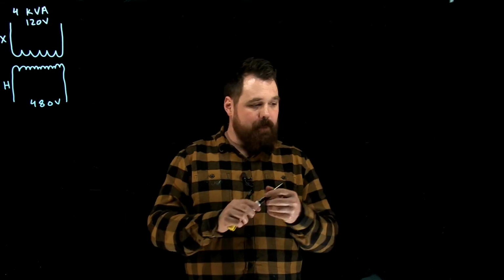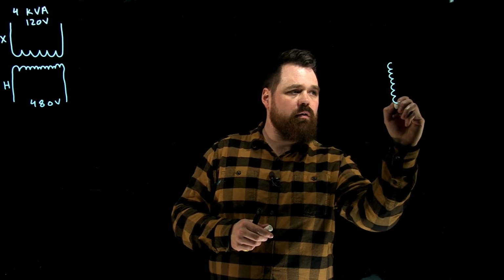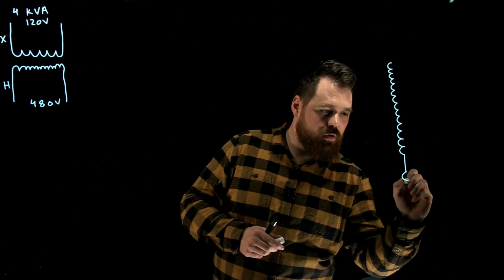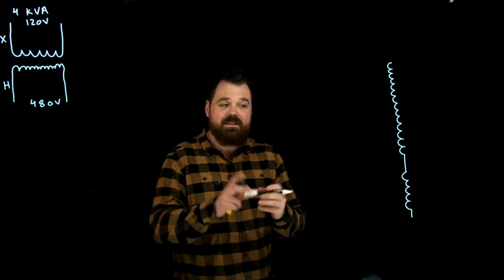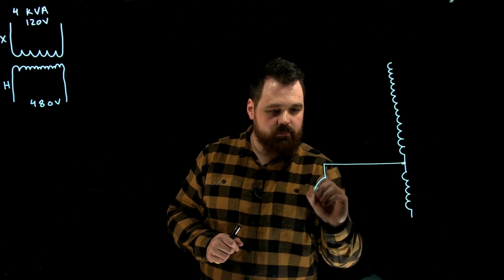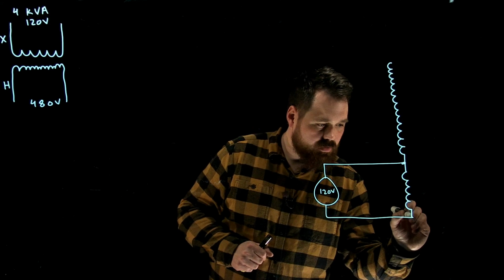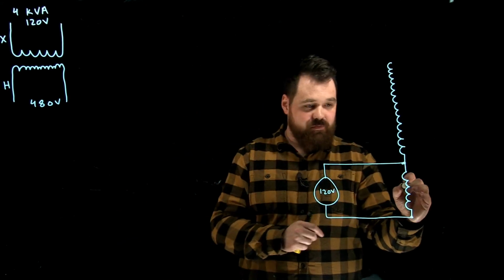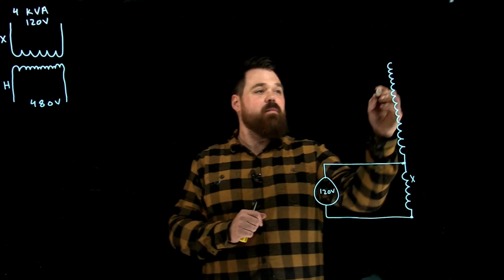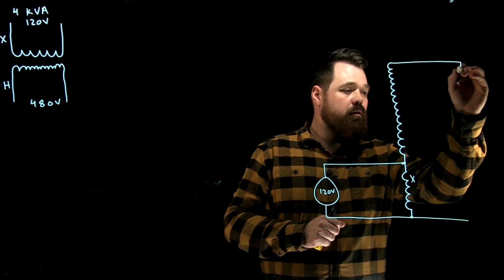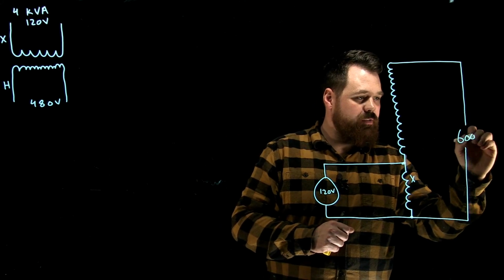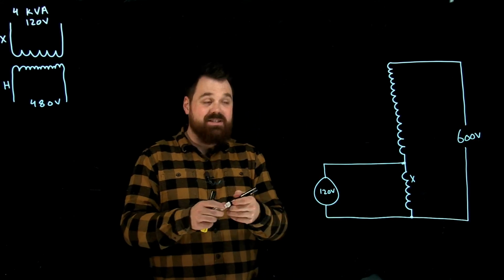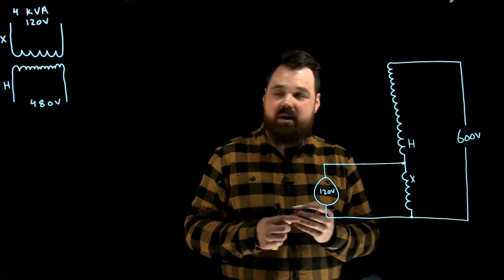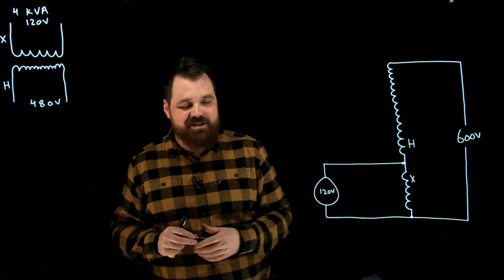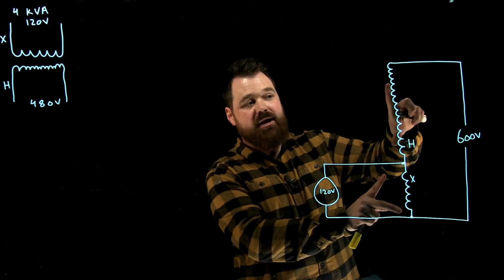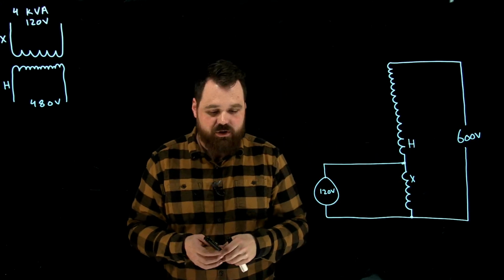Now we know an auto transformer is one big common winding. And I'm going to draw it like this, right? So we are going to take a 120 volt source, connect it still to this. This would still be my X winding, right? And we are actually going to connect it to provide us with 600 volts. Now what we have done, essentially, with this connection, here's my H winding, we've put those two windings in series like this. So we have a 120 volt source, 120 plus that 480 volt H winding is going to give us a 600 volt output.